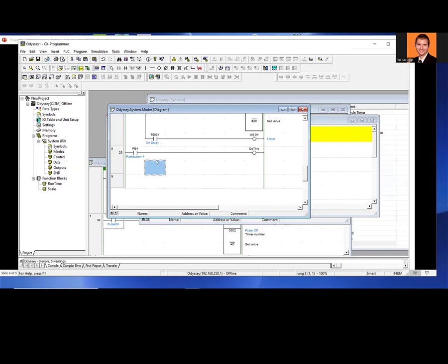And then if I wanted to run this, again, I would come up to this, and this says Work Online Simulator. And there is another option here, which is Start PLC to PT Integrated Simulation. What this does is this uses an internal server, and it reads and writes from the server, and then things like a SCADA system or an HMI could also read and write to that server, and you might be able to run, for instance, multiple PLCs. So this is pretty powerful for a register-based system. Does a lot of different things.